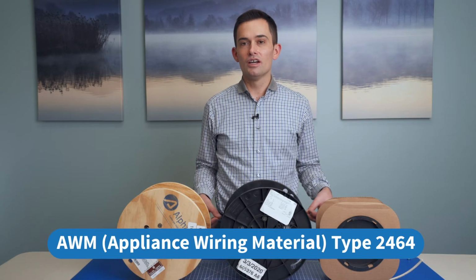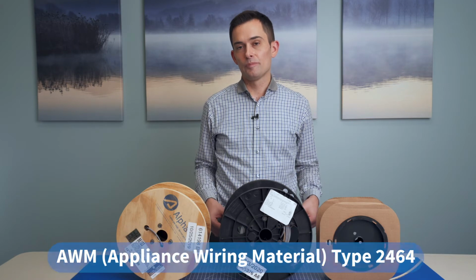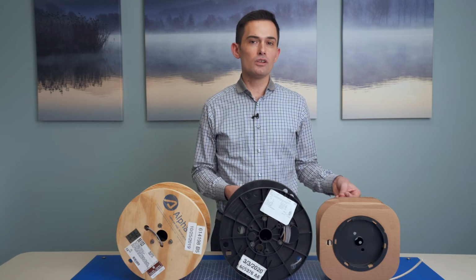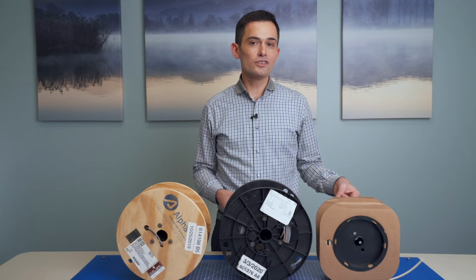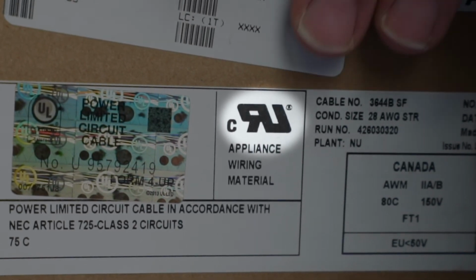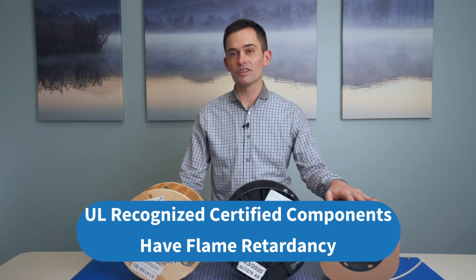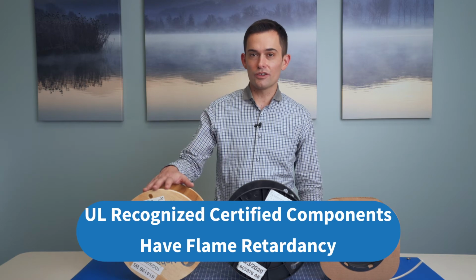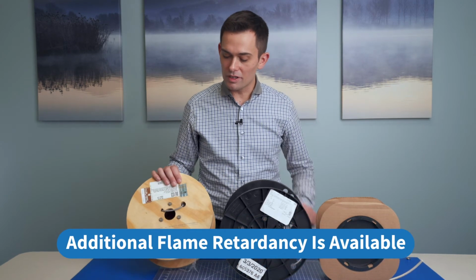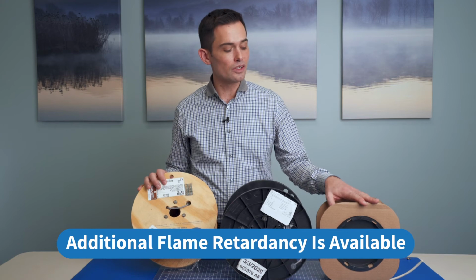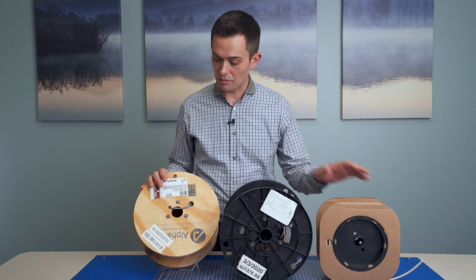volts. When it comes to jacketed multi-conductor cable, the most commonly used is AWM, which is appliance wiring material, type 2464. This is a good general purpose cable. It is UL recognized. It's not a listed product. All wire and cable that has the recognized component certification symbol on it, the backwards RU, has been tested for flame retardancy. There are more stringent standards available, and those can easily be differentiated between the recognized component type cables.